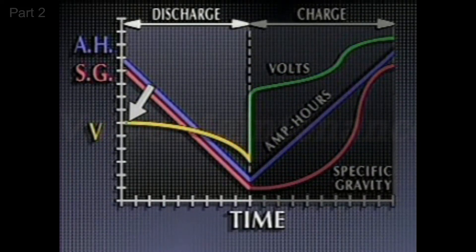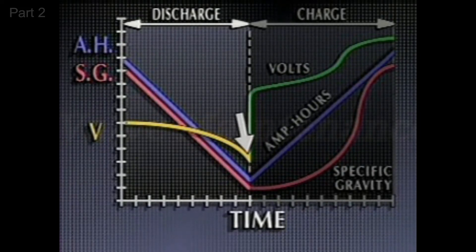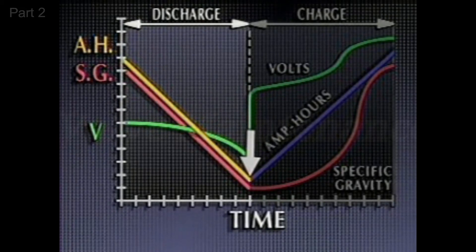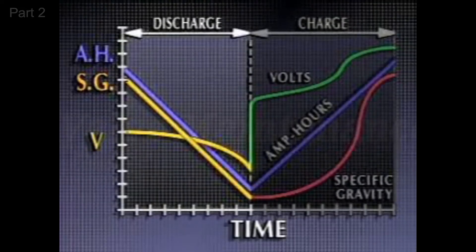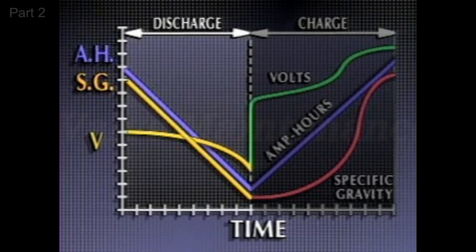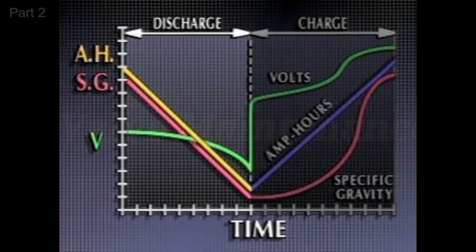When a fully charged cell discharges, cell voltage drops gradually. Then, when the cell is almost completely discharged, the voltage falls off rapidly to its final voltage. At the same time, the cell's ampere hours of capacity decreases at a constant rate, and the cell's specific gravity decreases at the same rate as the ampere hours. When the cell is discharging, its voltage, and especially its specific gravity, change at a relatively constant rate. So a measurement of either cell voltage or specific gravity during discharge will give a fairly reliable indication of how many ampere hours of capacity are remaining in the cell.